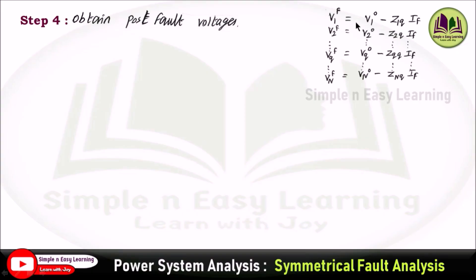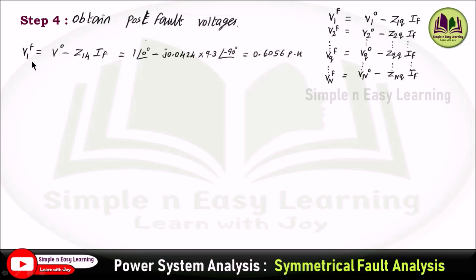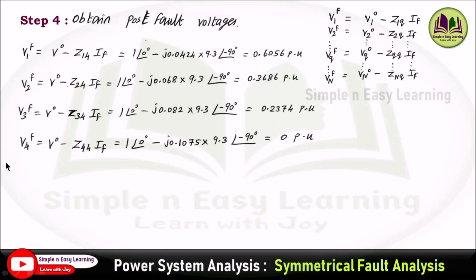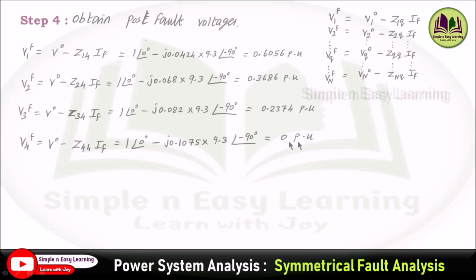Step 4: obtain the post-fault voltages using: V_i(f) = V_i(0) − Z_{iq} × If, where V_i(0) are pre-fault voltages assumed as 1∠0° and q = 4. Substituting values from the Z-bus matrix: V1(f) = 0.6056 per unit, V2(f) = 0.3686 per unit, V3(f) = 0.2374 per unit, V4(f) = 0 per unit.